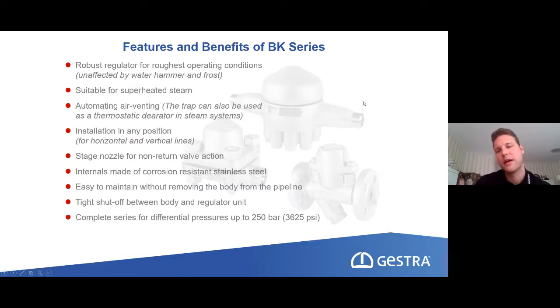So a BK is typical for steamline drainage because we have a little banking up of condensate on thermostatic steam traps, and the BK has a little more than the MK. So we have a little banking up in the drainage line, and then it will discharge again, and then it will bank up a little bit. This is okay if I have a steamline drainage with enough space before the steam trap, so that I can allow this little banking up of, it depends a little on the process, maybe 1 or 1.5 meters. Depends, as I said. But we should not use it on heat exchangers.